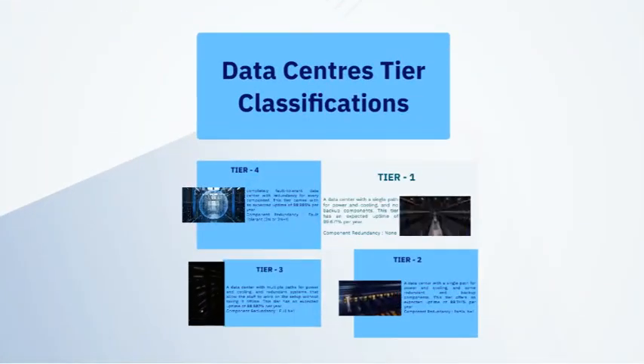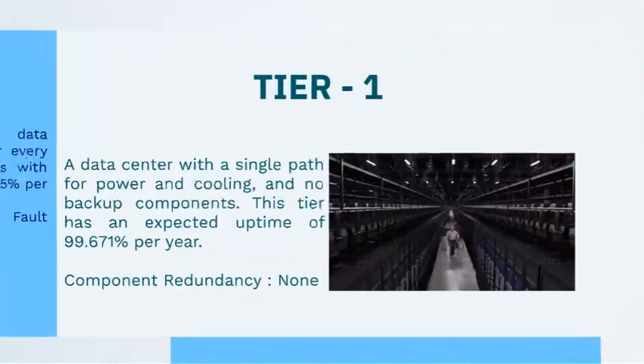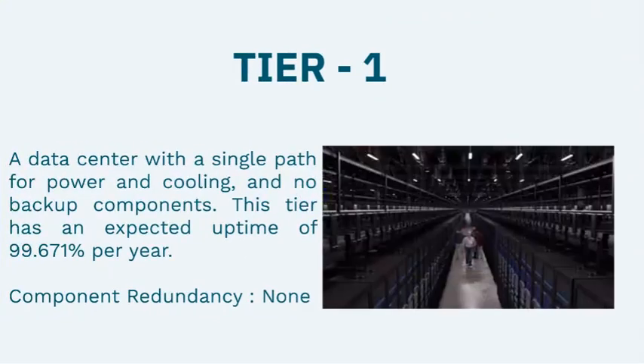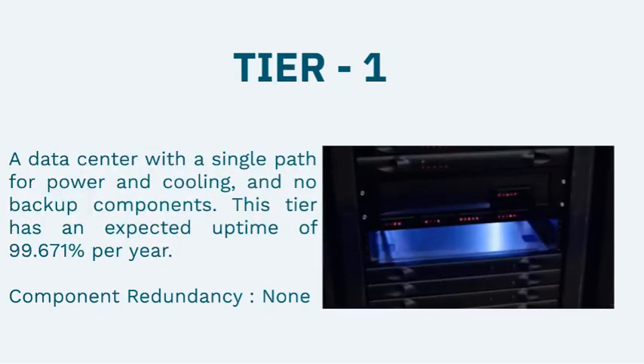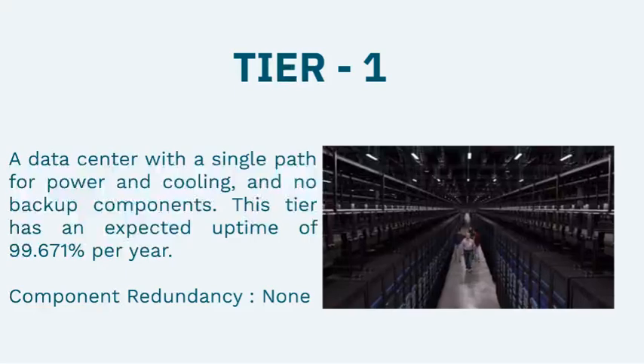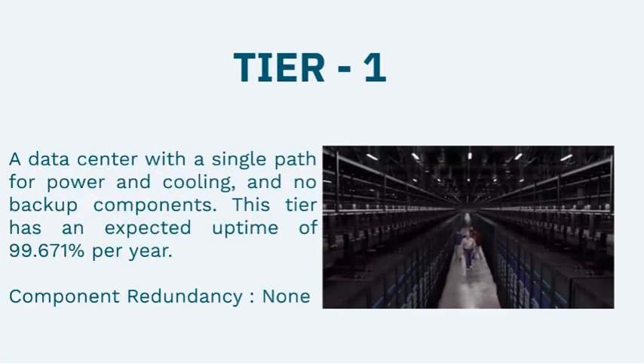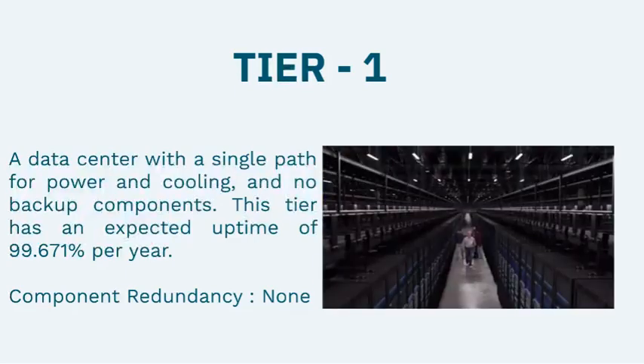The next section is data center tier classifications. First tier is Tier 1: a data center with a single path for power and cooling and no backup components. This tier has an expected uptime of 99.67% per year or less, since its component redundancy level is zero. So in case of fault, the client would have to suffer discontinuity ranging from a few minutes to several minutes or a couple of hours.